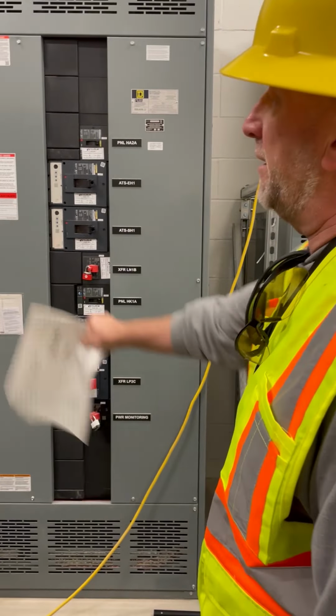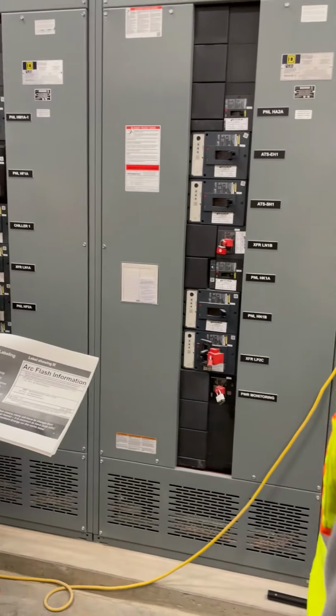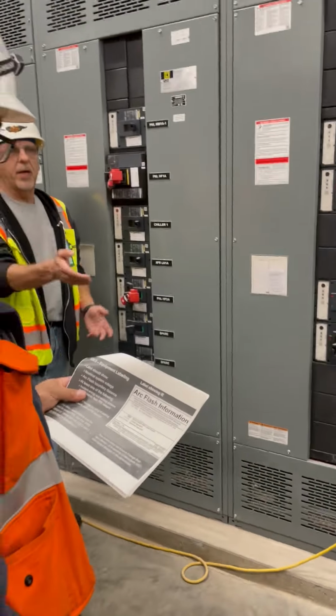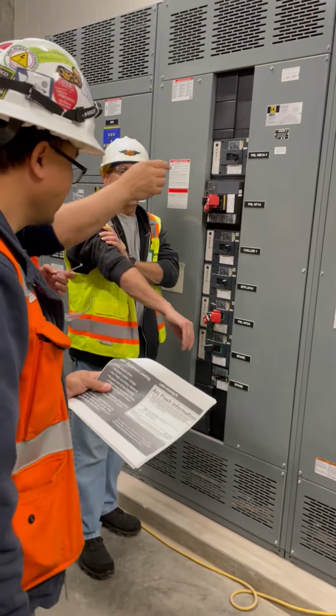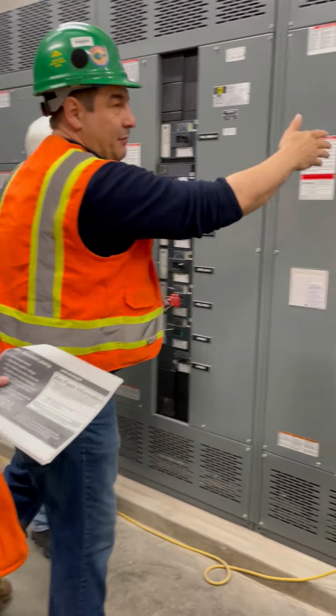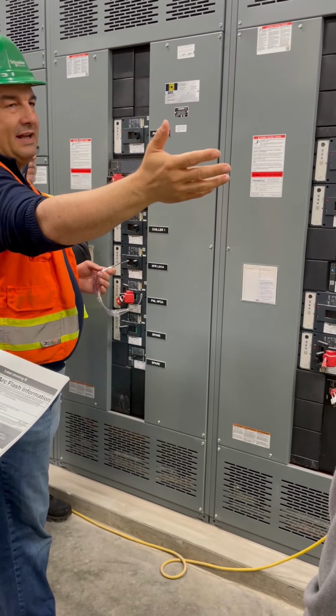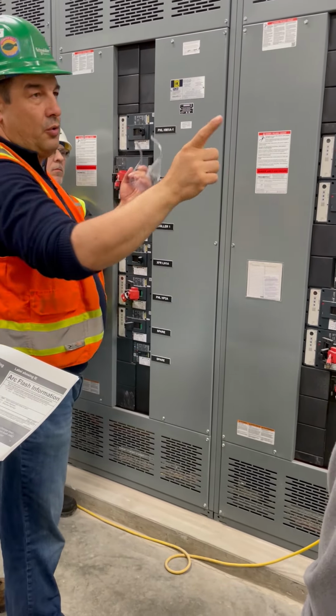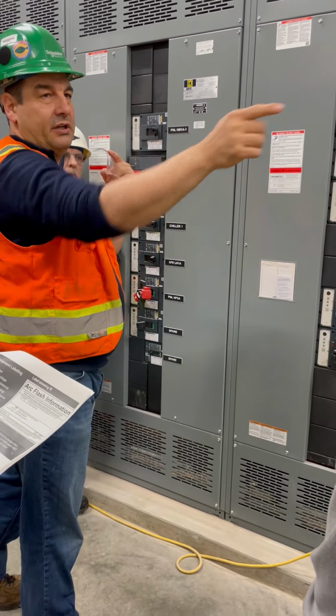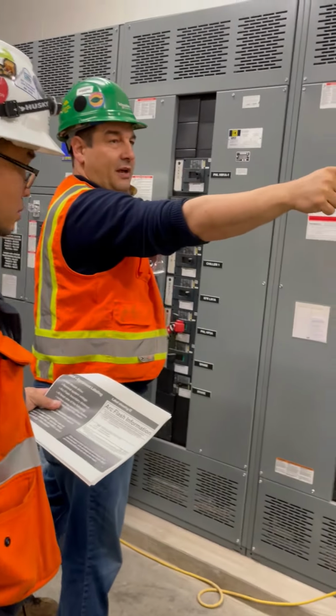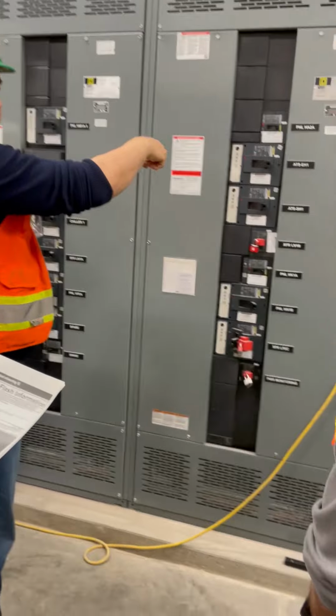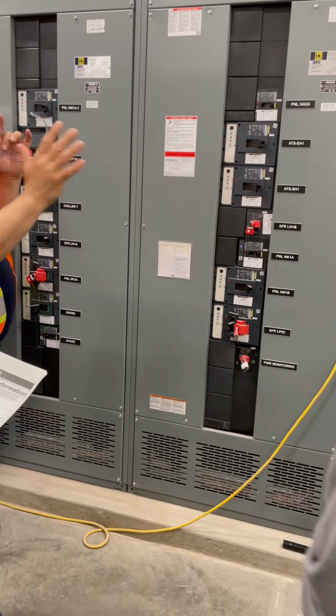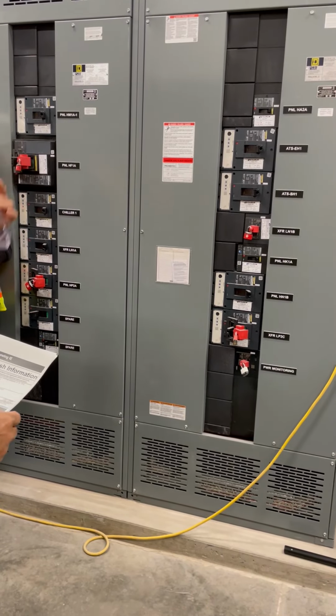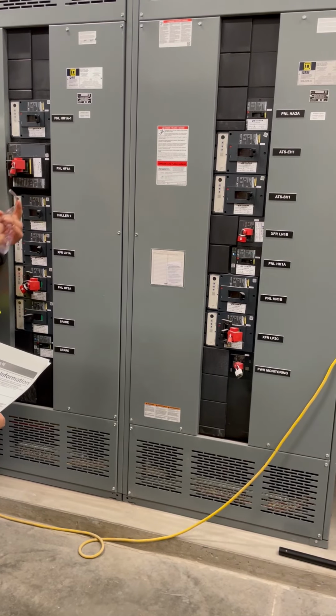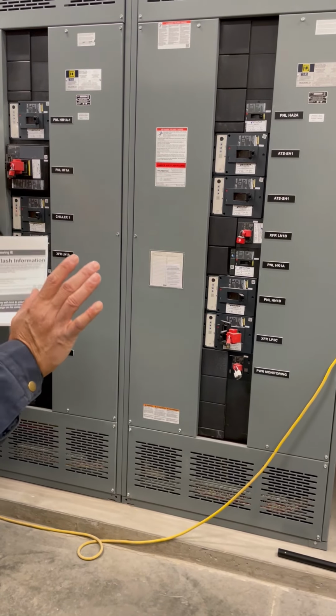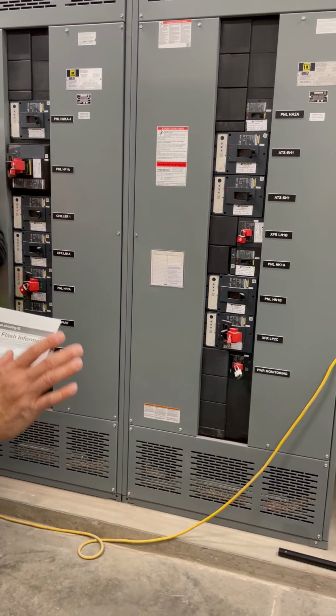Same breaker, different settings, different values, different situations. Usually that's kind of a study. And when you look at the breakers, this feeds a panel downstream. Those may or may not have breakers, but usually when you set and coordinate between this breaker and those breakers, in case of a fault, you want that breaker to trip first before it gets over here. So that's why those settings are really important, that they match and they're set correctly. That's the coordination portion of the study.